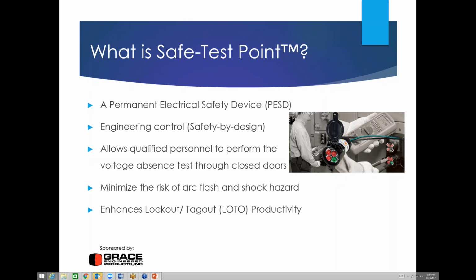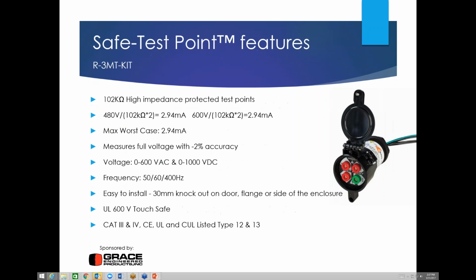It certainly enhances lockout tagout and productivity, and some of the key features of these devices are the built-in impedance. And really what we're doing here is taking the available energy and reducing it down to a low level. So at 480 volts on a 300 amp feed, the available current at the test points themselves is only 2.9 milliamps of current while we're doing our phase-to-phase and phase-to-ground testing. So there isn't a high potential there as we're going through that process.